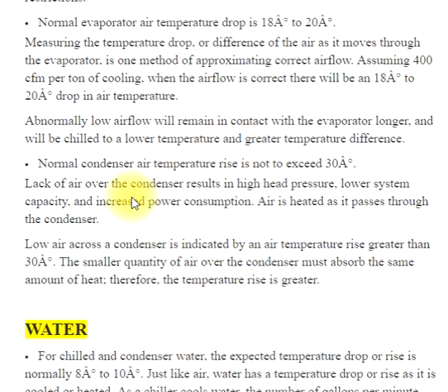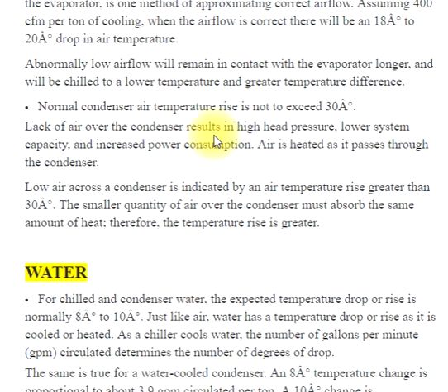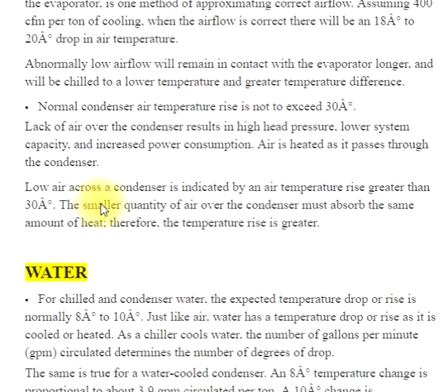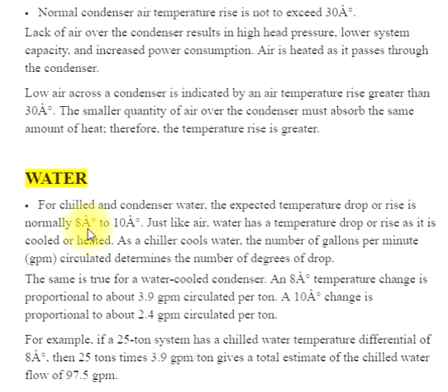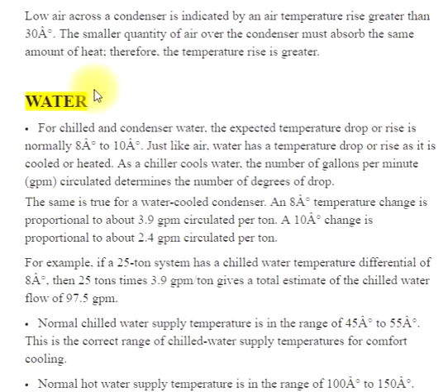Normal condenser air temperature rise should not exceed 30°. Lack of air over the condenser results in high head pressure, lower system capacity, and increased power consumption. Air is heated as it passes through the condenser. Low airflow across a condenser is indicated by an air temperature rise greater than 30°, since the smaller quantity of air must absorb the same amount of heat, causing a greater temperature rise.